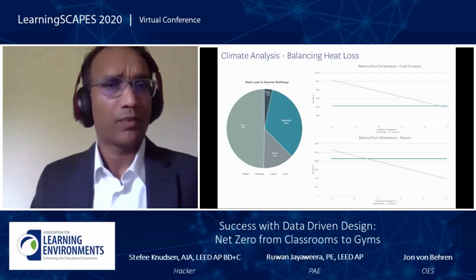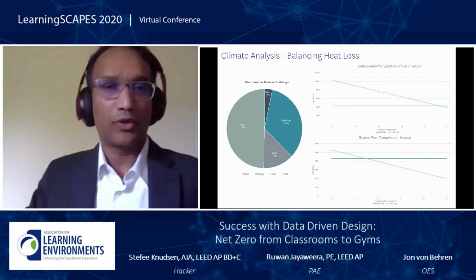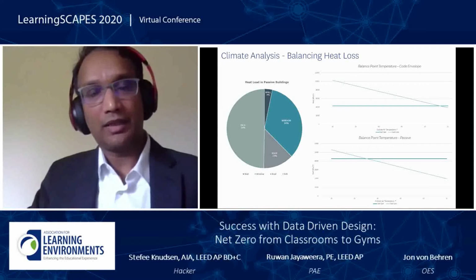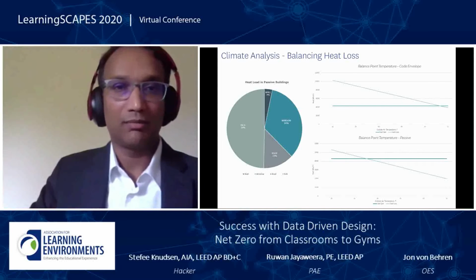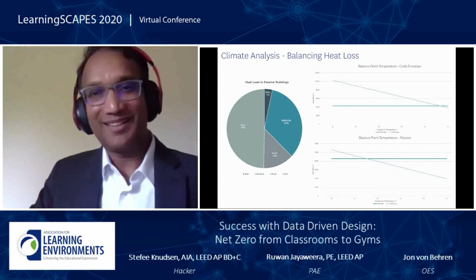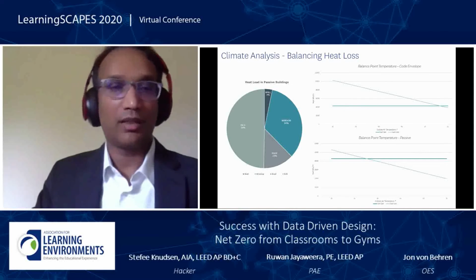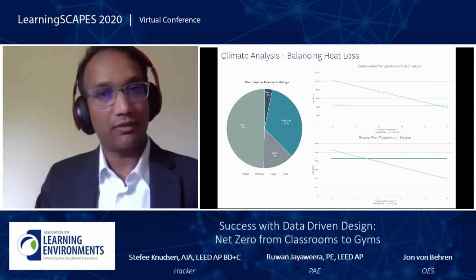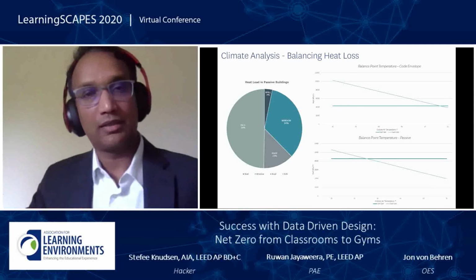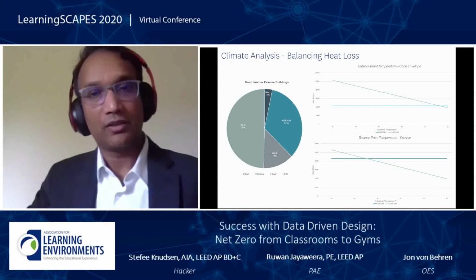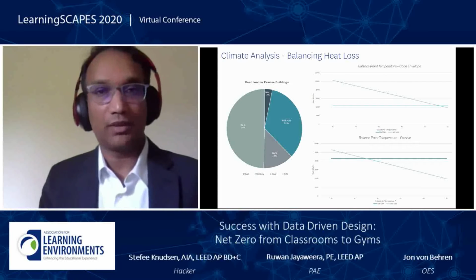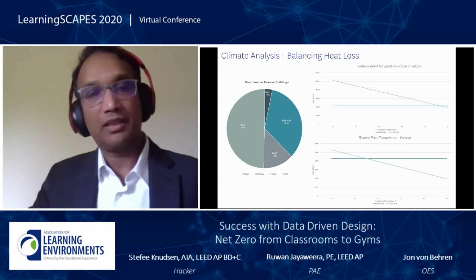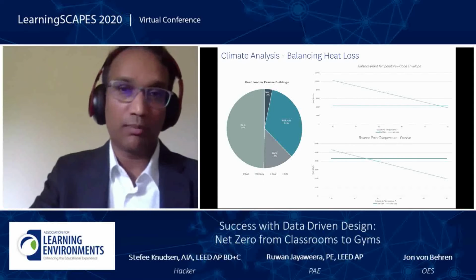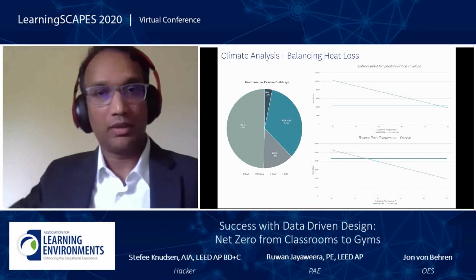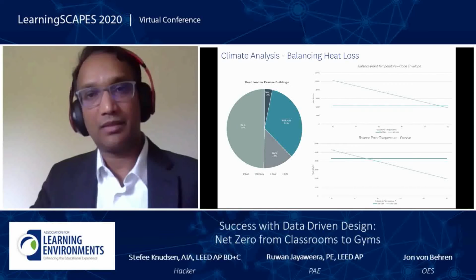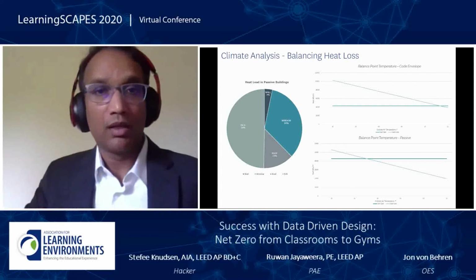Passive cooling is relatively easy, right? Basically you're balancing heat loss. In this case you have these two graphs - I know it's engineering speak, but play along. You get this horizontal line, which is essentially how much heat the people, lights, and computers give off. We assume it's pretty consistent at around 4,000 BTUs per hour, so that's a rate of heat being generated in the space - think of it as a heater. This other line is how much heat is lost through the envelope, because it's warm inside and cold outside, so heat leaves the space. How fast that heat leaves depends on how cold it is outside.